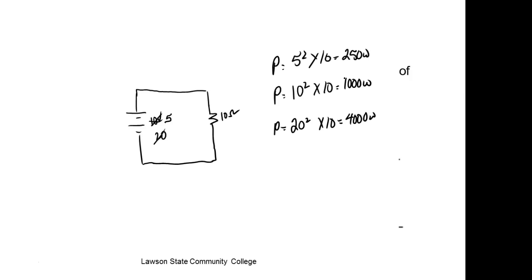My mother called me out to her house one time and said, Rich, my electric stove won't even boil water anymore. I went out there and measured her 240, and it was only 120 volts. So her outlets were only putting out a quarter of the power, right? What had happened is she had lost one of her drops coming down from the transformer. We had to call the power company. But as soon as I measured the output coming out of that outlet, and it said 120 volts, I knew she had big problems, right? That makes sense.